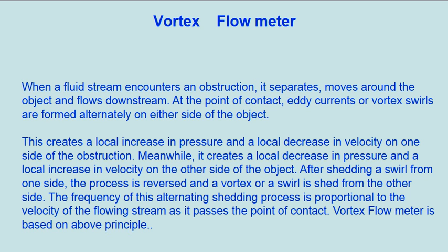After shedding a swirl from one side, the process is reversed and a vortex or swirl is shed from the other side. The frequency of this alternating shedding process is proportional to the velocity of the flowing stream as it passes the point of contact. The Vortex Flow Meter is based on this principle.